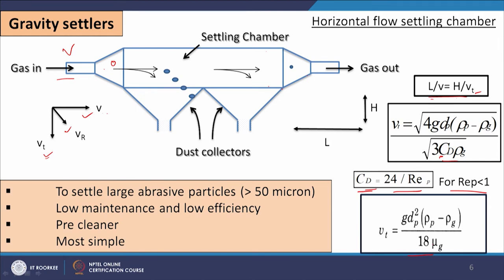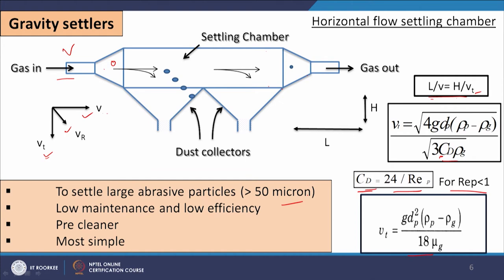This expression is for the terminal settling velocity of a particle falling in the laminar zone where the particle Reynolds number is less than 1. Gravity settlers are very simple and not costly. They are useful to settle large abrasive particles greater than 50 microns. They have low maintenance, low efficiency, and are considered as a pre-cleaner. For separation of very fine particles this may not be a good device, but for relatively larger particles it is a good and simple option.